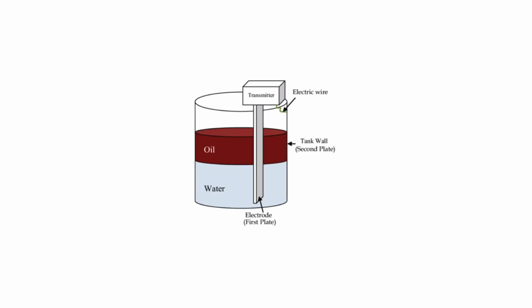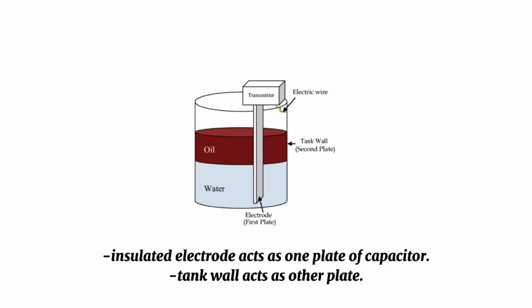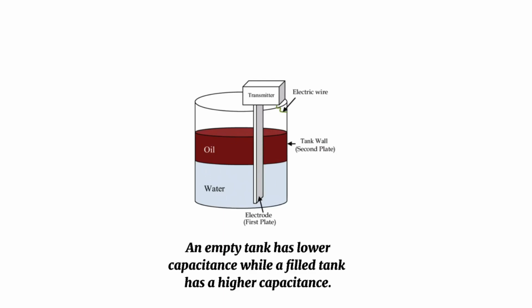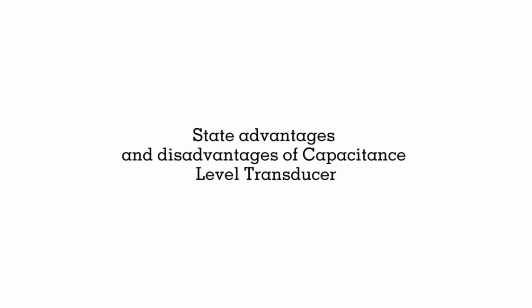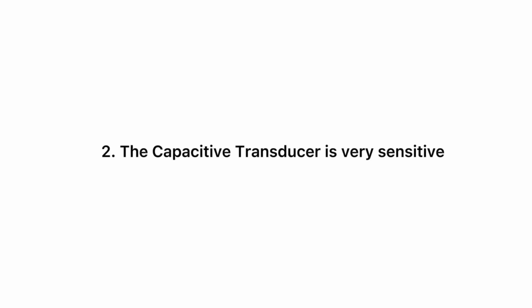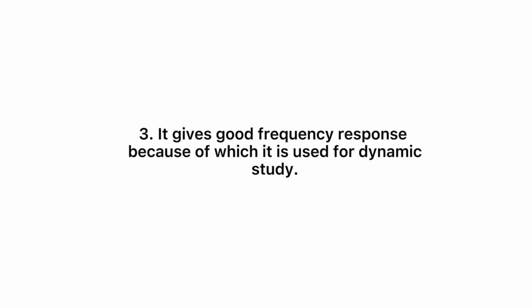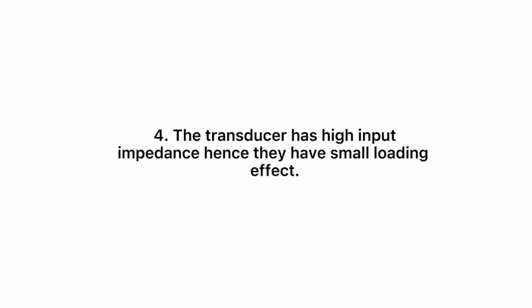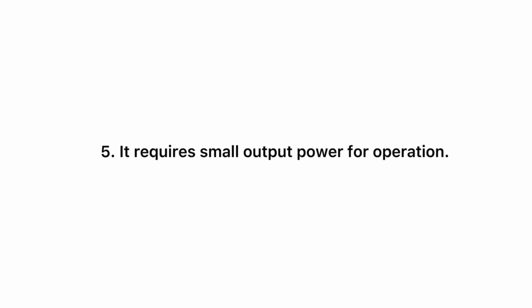The principle of capacitive level measurement is based on a change of capacitance. An insulated electrode acts as one plate of the capacitor and the tank wall acts as the other plate. The capacitance depends on the fluid level. An empty tank has a lower capacitance while a filled tank has a higher capacitance. Advantages of the capacitive transducer. First, it requires a small external force for operation and hence is very useful for small systems. Second, the capacitive transducer is very sensitive. Third, it gives good frequency response, because of which it is used for dynamic study. Fourth, the transducer has high input impedance, hence a small loading effect. And the last one, it requires small output power for operation.